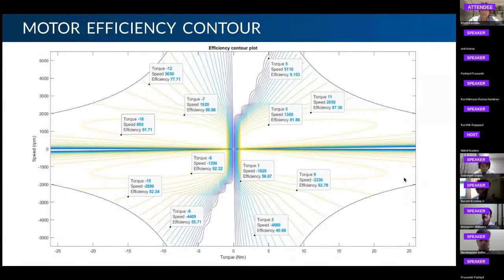Now we can move on to the inverter design. Yeah, so for the inverter design, the design requirements were that we require a variable voltage, variable frequency supply with a 48 volt peak phase-to-neutral value. And so for this, we have used a basic three-phase voltage source inverter with a DC link capacitor to limit the ripples.